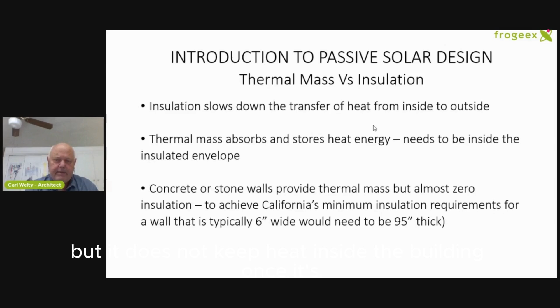People often think of thermal mass as the same as insulation, but it's very different and functions differently. For example, a concrete wall has very little insulation value. The California minimum standard for an exterior wall, which is 6 inches wide, would need to be 95 inches thick in concrete to provide the same insulation value. So concrete is good for thermal mass to store heat, but it does not keep heat inside the building.